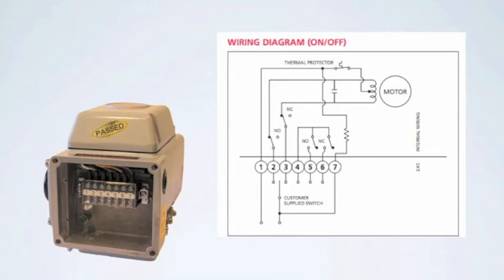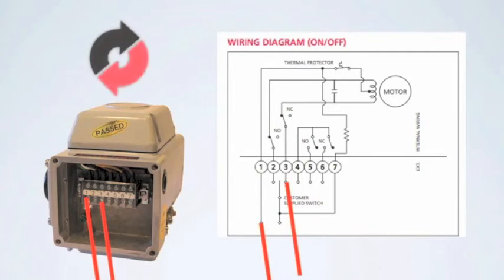To close or drive the actuator in the clockwise direction, apply power to Terminal 1 and Terminal 3. The actuator will turn clockwise until it reaches the internal limit switch and shuts off.